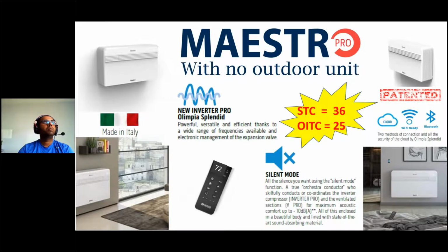So the Pro unit just came out in 2019. They're selling like hotcakes. Where I told you earlier that the Smart is a single stage on-off rotary compressor, this is an inverter driven model. So it has the ability to control its capacity from 35% to 100%. It has ECM motor technology in the outdoor coil and the indoor coil.